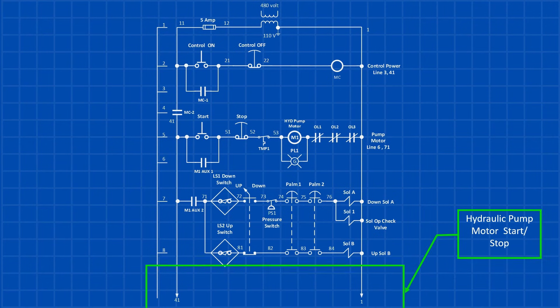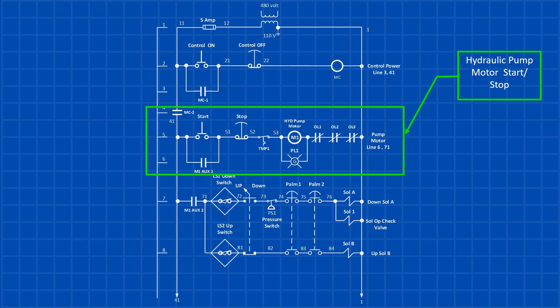The next rung in the ladder diagram controls the hydraulic pump motor starter. Like the master control circuit, it's a latching circuit but includes additional interlocks, a hydraulic temperature switch, and a motor overload protection contacts. When the start push button is pressed, the motor begins running.